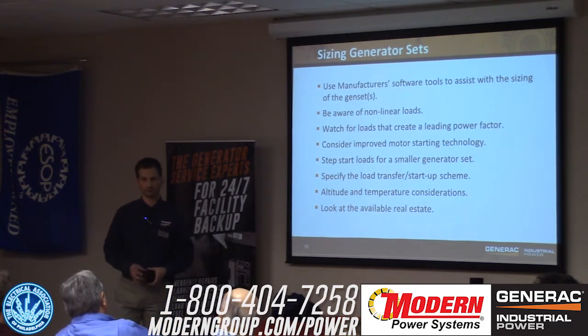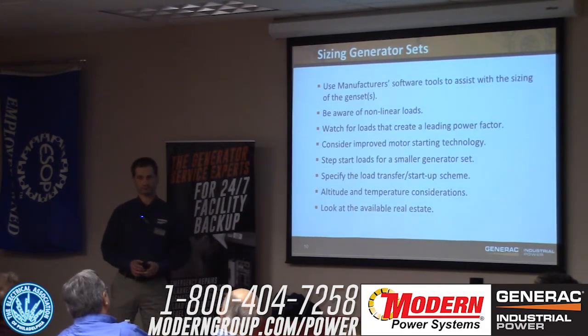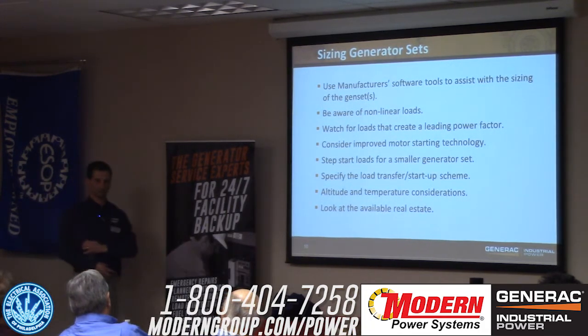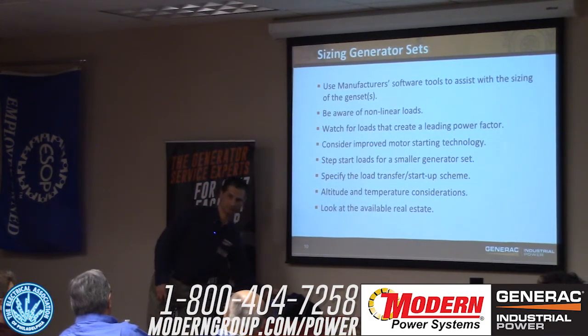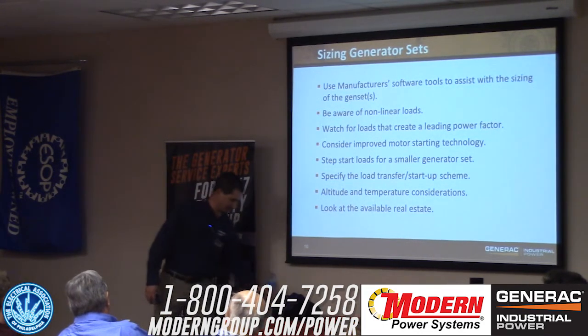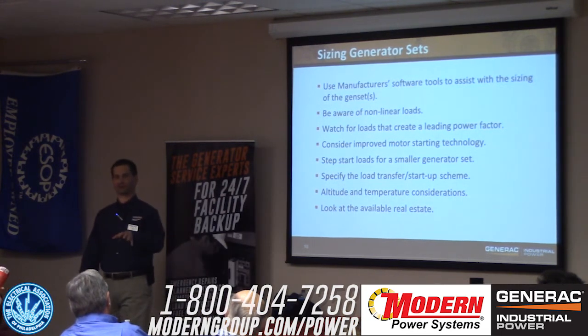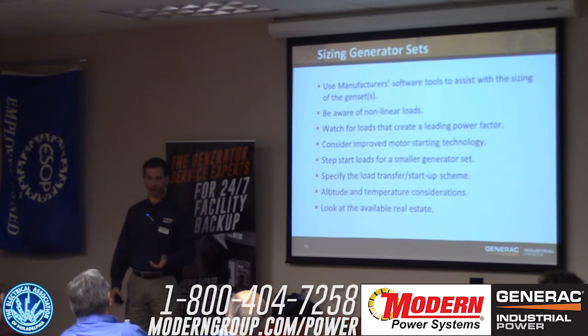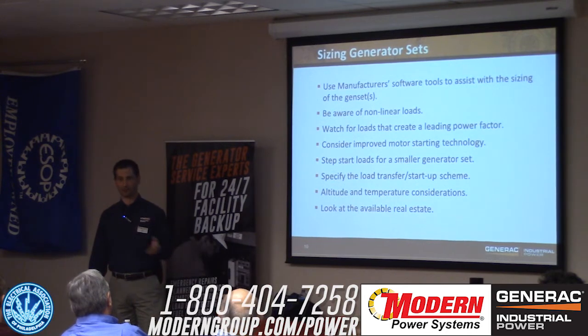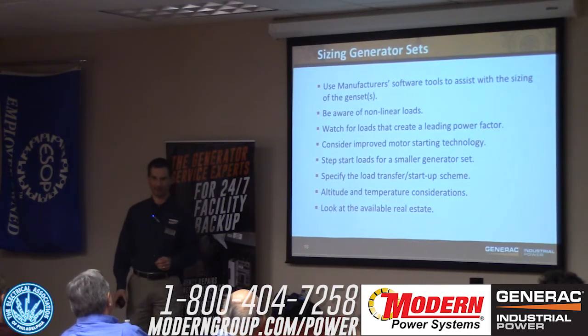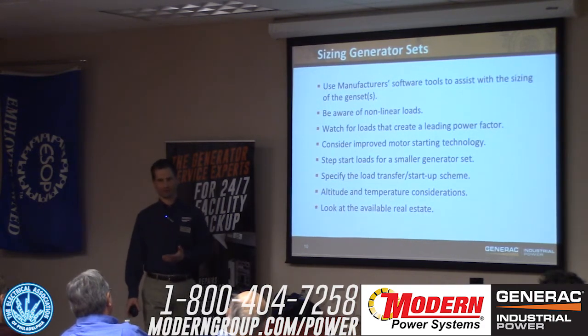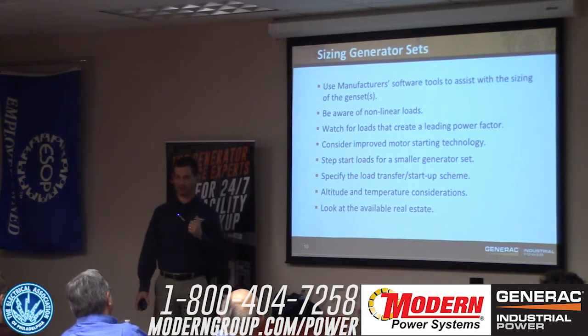Go ahead. Question about the VFDs. If you do take advantage of the VFD and you downsize the alternator and the customer has a reason to bypass the VFD, do they know that they're not going to be able to run that equipment during that time? Well, yes, and it depends. Actually, that's a great question because it plays directly into especially fire pumps. Anybody that's started a fire pump, I can't have more than a 15% voltage dip on a fire pump when I do a normal starting technique, like with a VFD. If I have to bypass that VFD and do an emergency start, the genset still has to do it, but it can be ugly. It could be a 25 or a 30% voltage dip, but the generator still has to be able to do it.